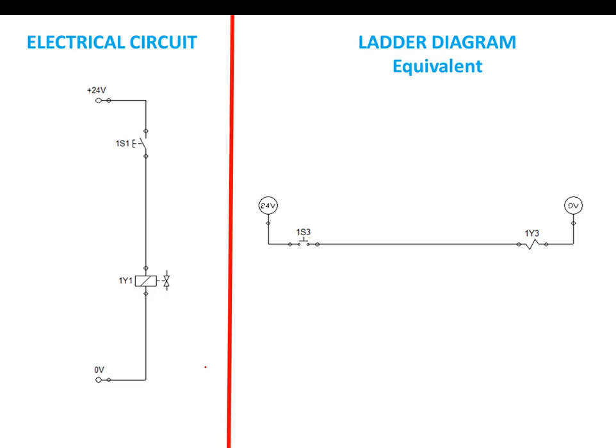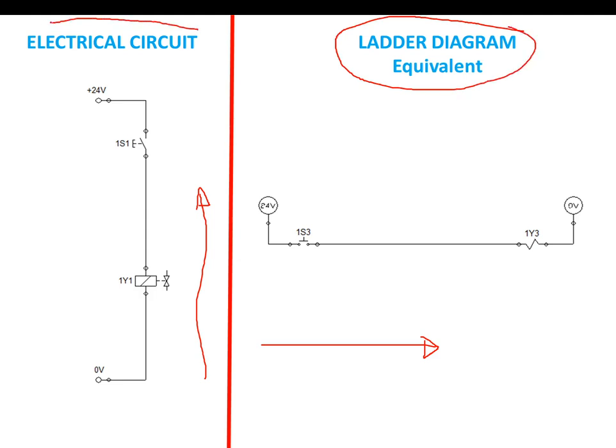It is helpful to know that an electrical circuit is always shown in vertical orientation, whereas a ladder diagram is always shown in horizontal orientation. Both of these circuits have exactly the same function. The only difference is the way of presentation. The vertical lines are called rails — where power is sent through — and the horizontal lines are called rungs, where the components are placed.